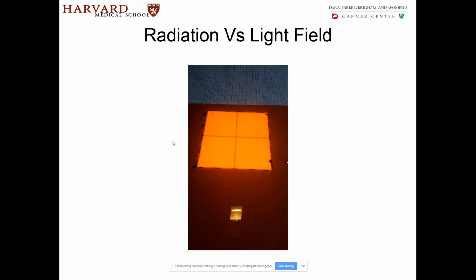What's going on? Maybe the light field is off in terms of orientation. Maybe the radiation field is off. So in this case, you see a radiochromic film being placed here. Then we open the jaws, say this is 10 by 10, mark out the borders of that with a pen, then go outside and irradiate the film.